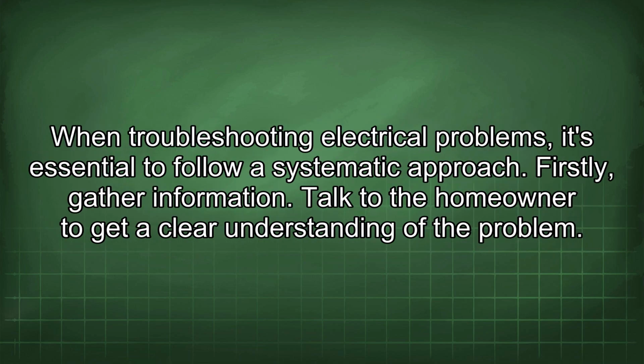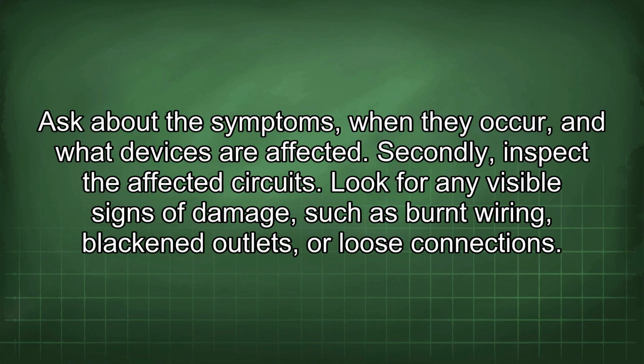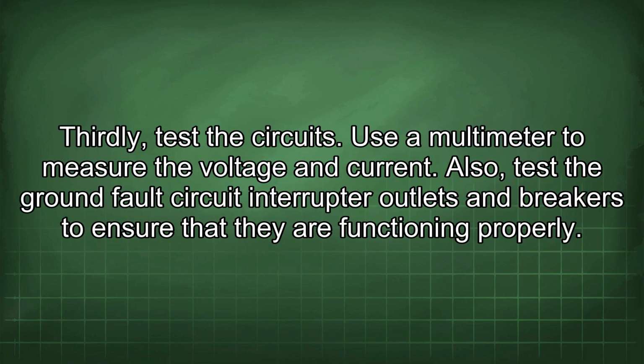When troubleshooting electrical problems, it's essential to follow a systematic approach. Firstly, gather information. Talk to the homeowner to get a clear understanding of the problem. Ask about the symptoms, when they occur, and what devices are affected. Secondly, inspect the affected circuits. Look for any visible signs of damage, such as burnt wiring, blackened outlets, or loose connections. Thirdly, test the circuits. Use a multimeter to measure the voltage and current.